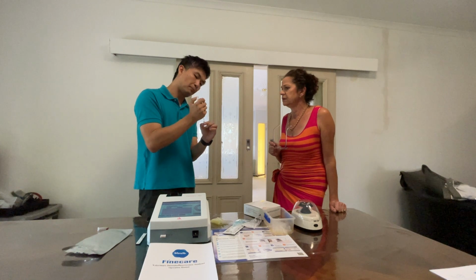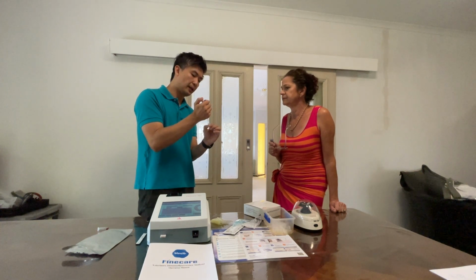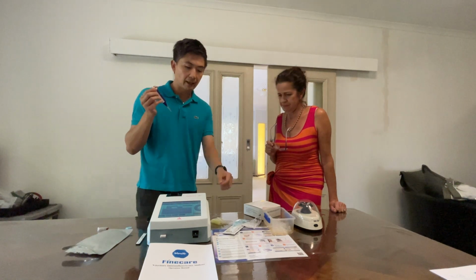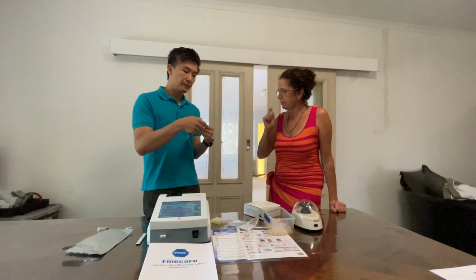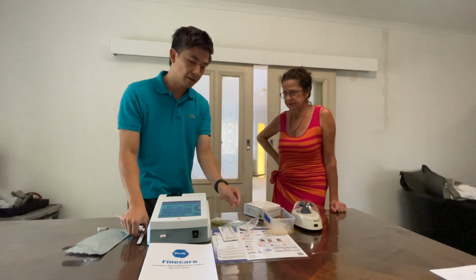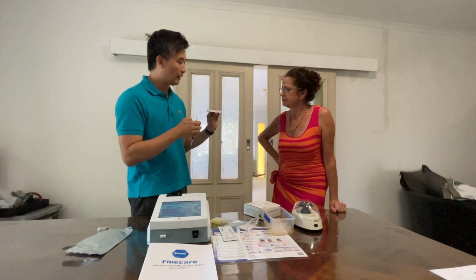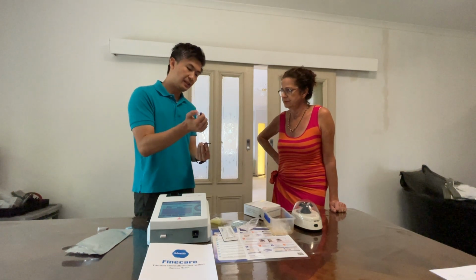Okay, and now we reset, let it go back to the top. Okay, and then now we can just go down to the first stop, slowly take the liquid up. It's already set at a certain volume for you, so you don't really have to do any tweaks to this. That's good. Yeah. Okay, so you have the solution to be tested, and now you want to take your cassette. Open the pack, and I'll just use one that we've used earlier. This is a test cassette. Lay it down on a flat surface, and you want to drop everything in the pipette into this little well here. Yes. Okay. Yep. So do it gently, and make sure you go all the way down to the second stop. Yep. Okay. And then now it's ready to be tested.